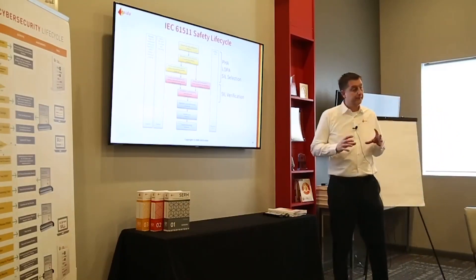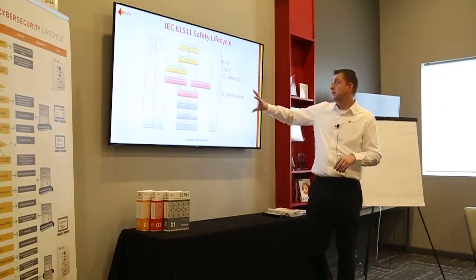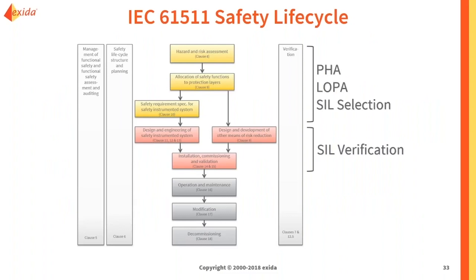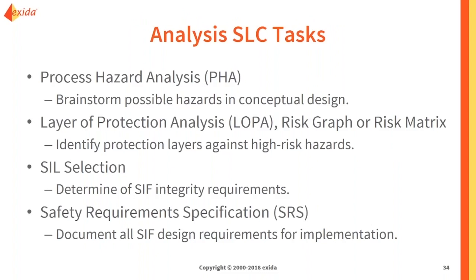When determining your target SIL level, we're in the analysis phase of the life cycle — the PHA and LOPA/SIL selection phase. In this phase we do process hazard analysis to identify potential hazards, then layer of protection analysis, risk graph, or risk matrix to identify protection layers and overall risk levels. Then we do SIL selection to specify the integrity requirements the safety instrumented function must meet, and document everything in a safety requirements specification.